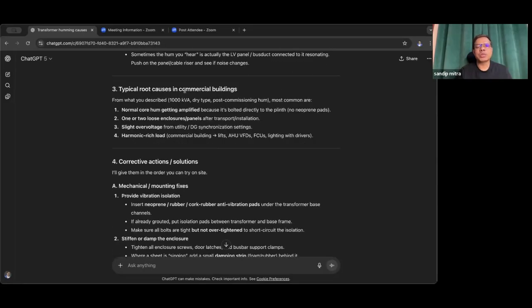The typical root causes in a commercial building. From what you described, a 1000 kVA dry type with post-commissioning hum, the most common is normal core hum getting amplified because it's bolted directly to the plinth.